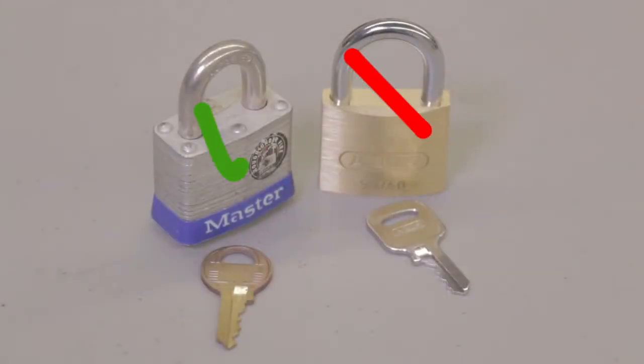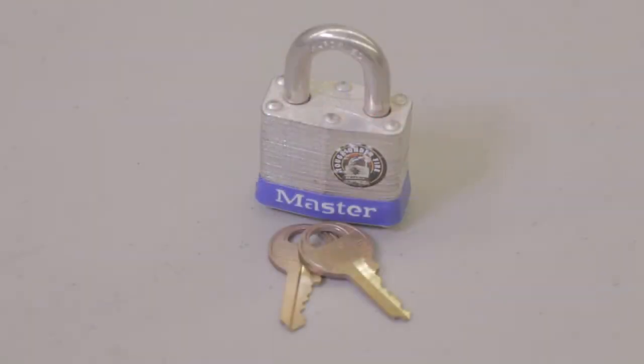Plant Services only use board-approved devices for a lockout/tagout. Never use board-approved locks for anything other than a lockout/tagout. These locks represent a potential danger, and we don't want people to stop taking them seriously. Replacement locks are issued by your supervisor. If you've received a replacement lock, one of its two keys must be destroyed for safety reasons. One key per lock will prevent someone from mistakenly removing it when they don't have authority over the lockout.